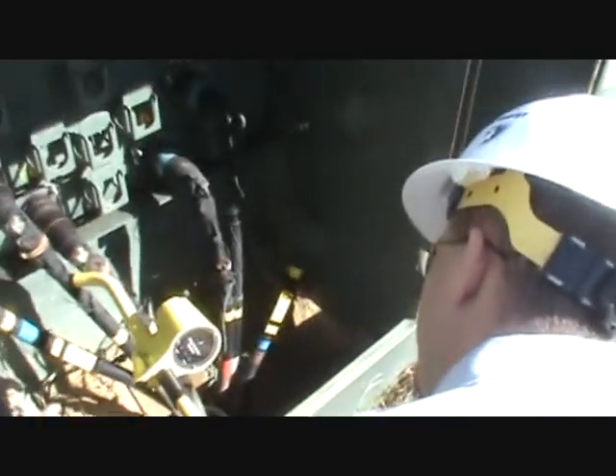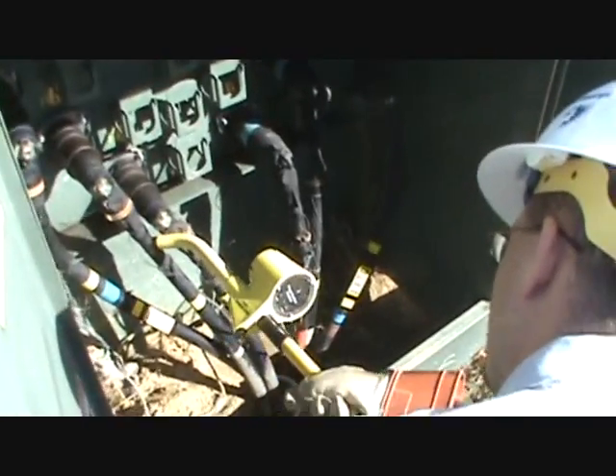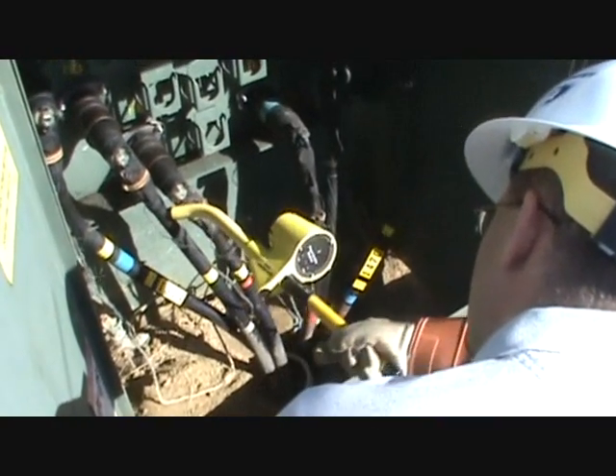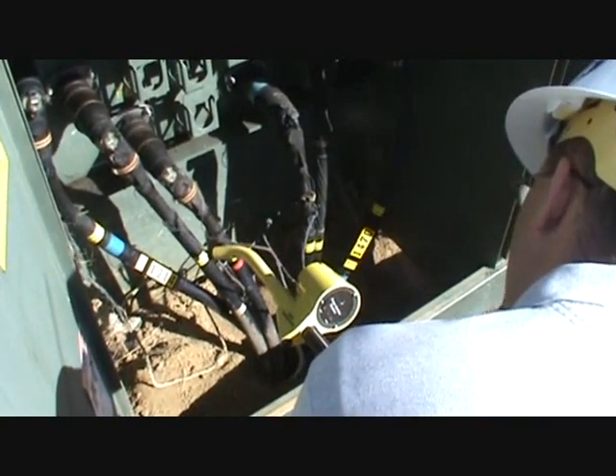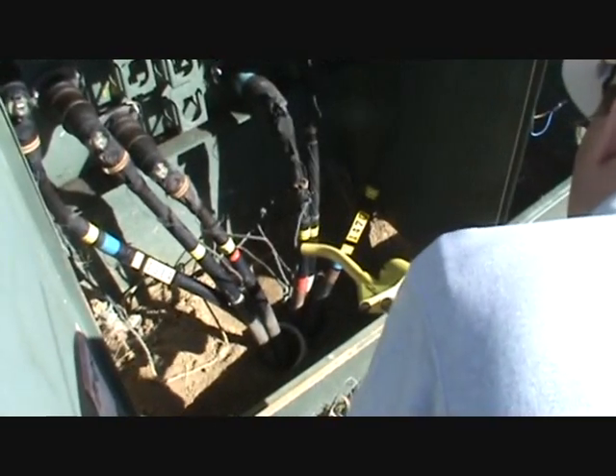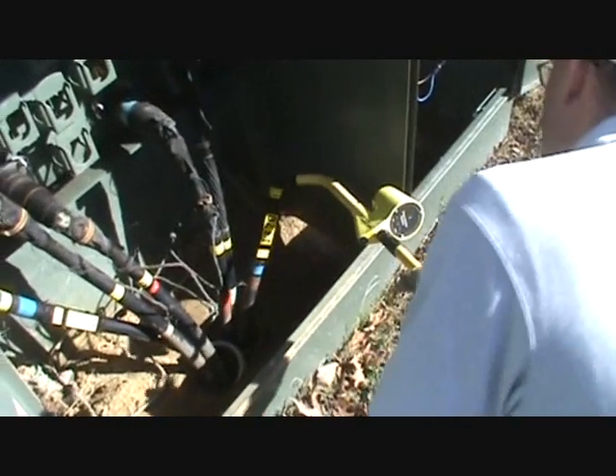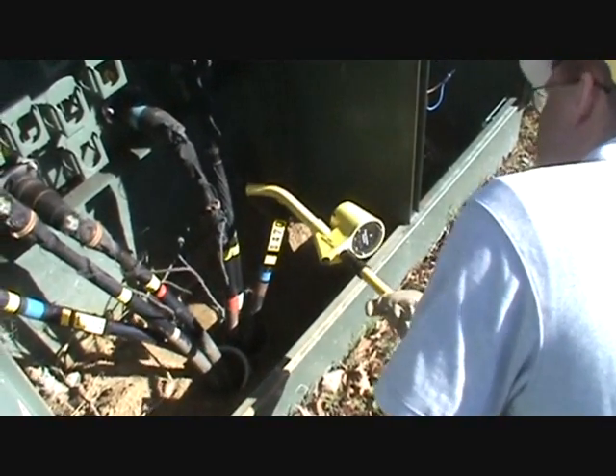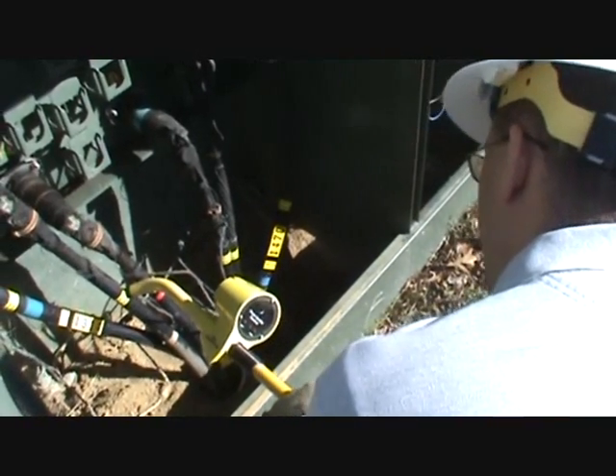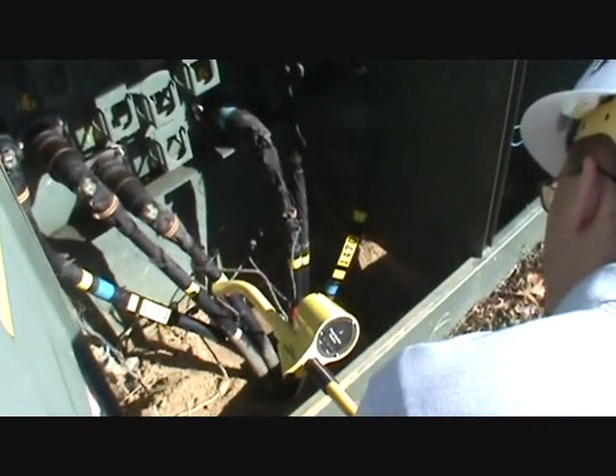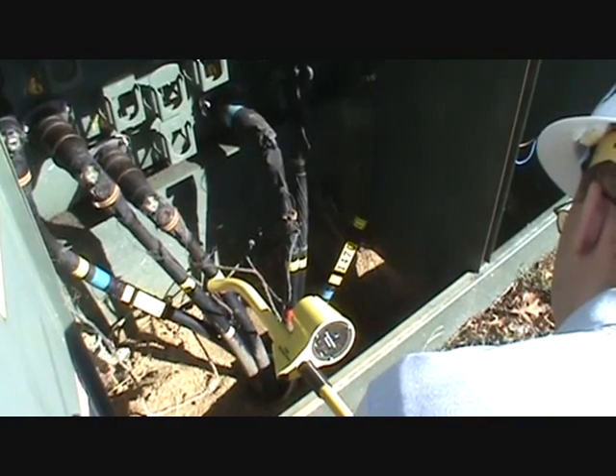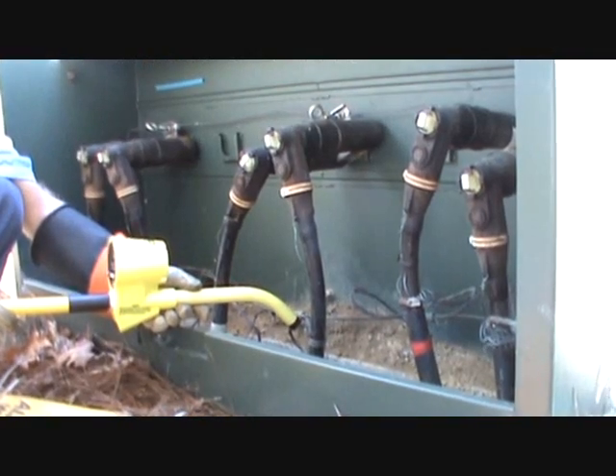See it beeping down? Now if we were able to pick it up on the primary, it would beep the other way, but we'd probably have to go phase to phase. The easiest way is to go to the neutral here. Now over here, it's not going to beep anywhere on any of these other cables, it's only going to beep on the source cable feeding this transformer. Y'all got it? See the beep?